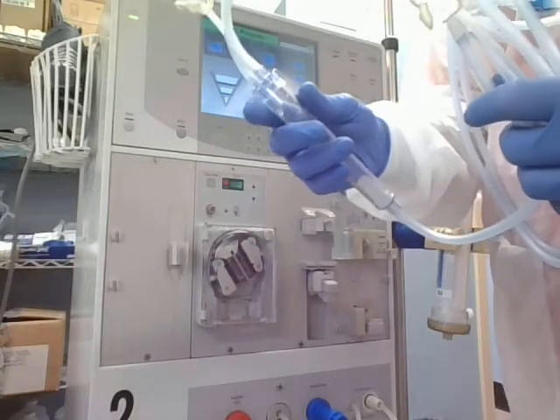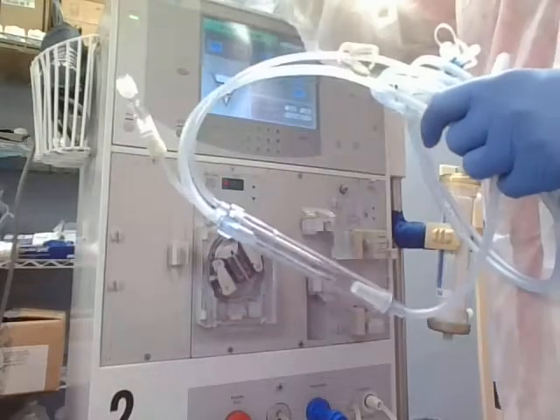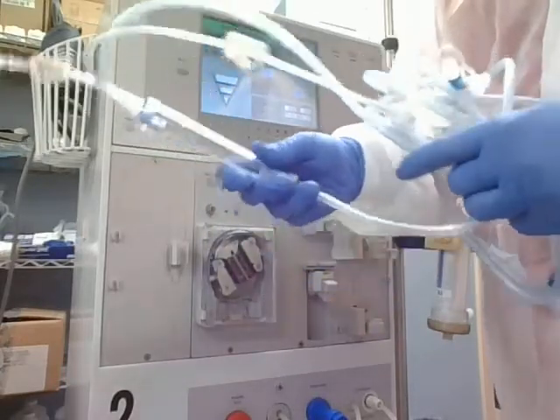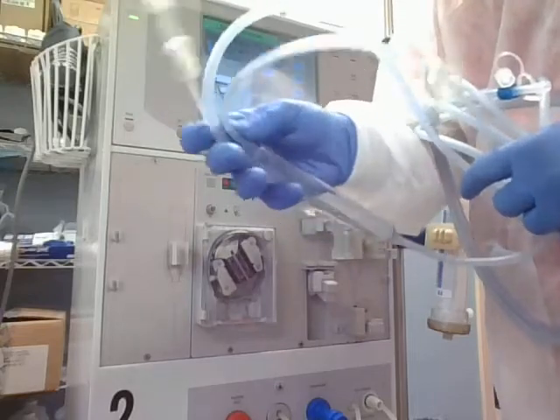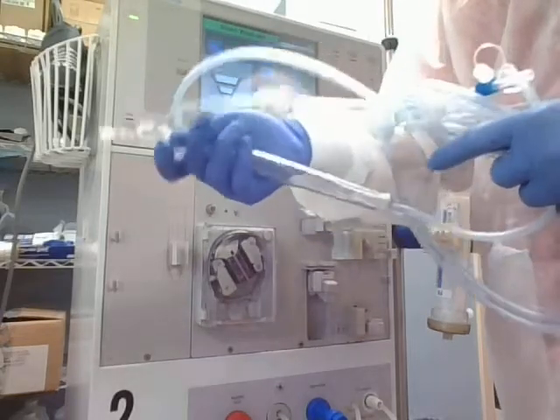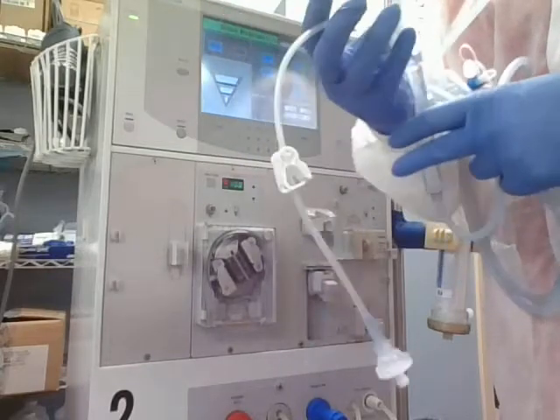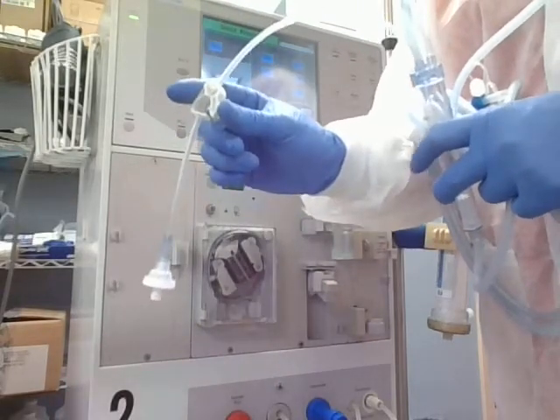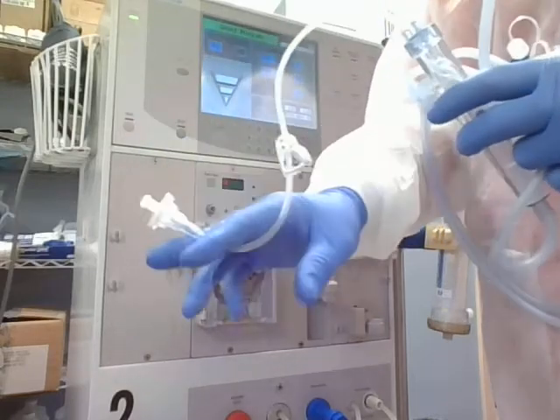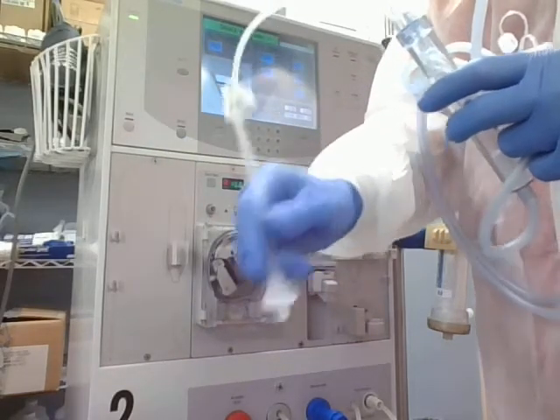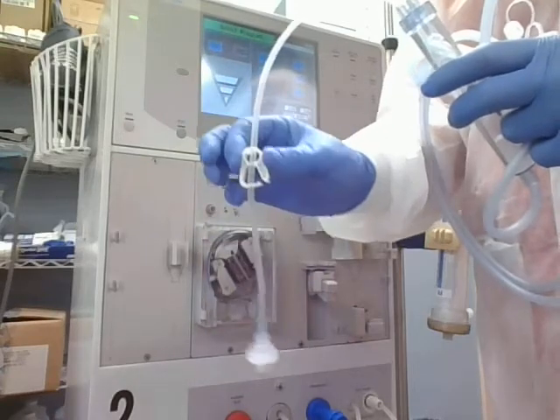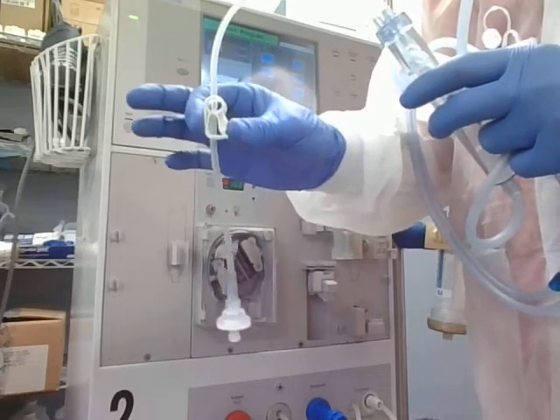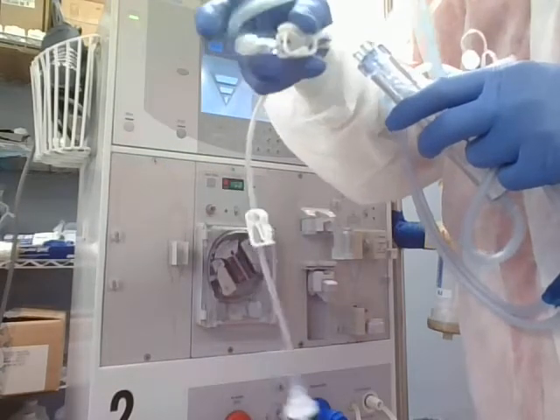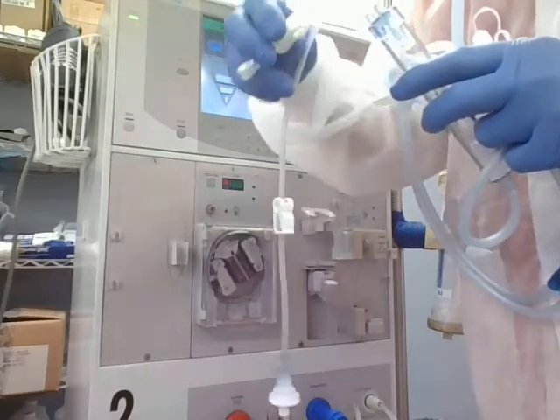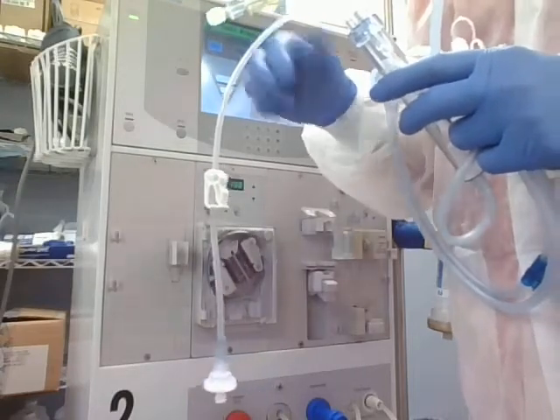On the venous drip chamber, there are 3 lines going into this venous drip chamber. Tear that piece of paper off so that your lines are completely free. The first line is our medication line. It's just a little short line where we can put medication, or where your nurse can put medication. The second line has your transducer protector on it. So this is your transducer line. As soon as you take it out of the bag, you want to make sure that you clamp that closed. You can go ahead and clamp your medication line closed as well. This will come into play in a little bit whenever we get our saline hooked up.